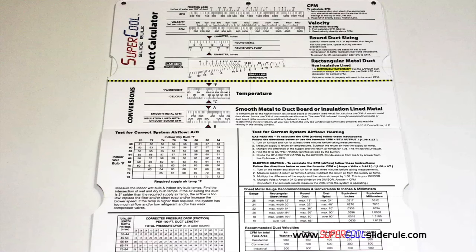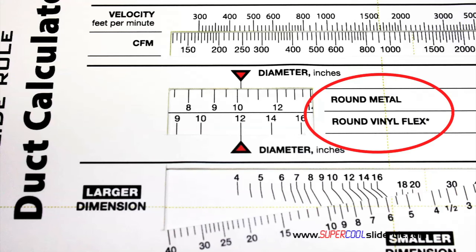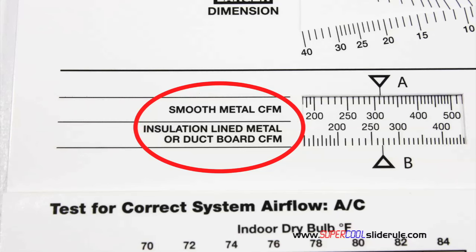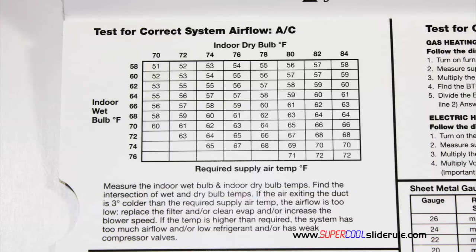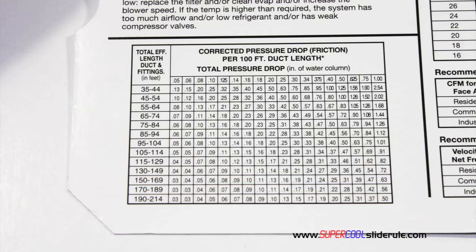Inside is packed with even more information. It performs sizing of both metal and flexible duct. It has the only direct reading conversion from smooth metal to insulation lined metal we've ever seen. The majority of technicians have never been taught that if the insulation is on the inside of the ductwork, you cannot size it with a regular duct calculator. It has step-by-step directions for determining airflow through a gas furnace, electric furnace, or an air conditioning unit. It has pressure drop multipliers for ductwork, as well as recommended velocities.